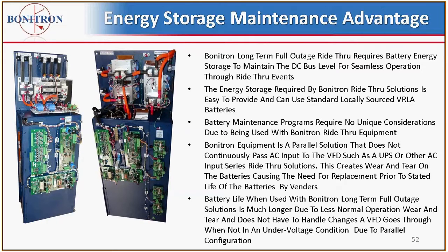Now, when we're talking about long-term full outage ride-through, over 2 seconds, outages, you're going to be using the battery ride-through booster, what we call the heavy-duty booster, the M3460B. So this also means that you're going to be adding energy storage to the actual ride-through boosters. We can provide the energy storage, or if you have a good source for batteries that knows what they're doing, because there are certain things that you have to do with a battery cabinet that make it a little bit different than normal electronics cabinets.